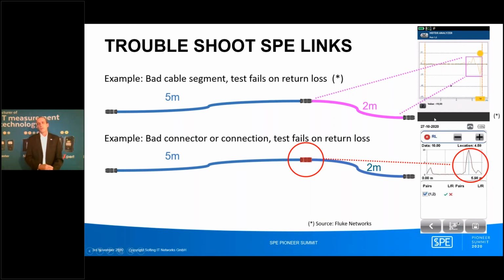With these additional functions, you can do a lot of troubleshooting in the field when you have a failed cable, and find out where along the cabling channel the problem is. I should note that both these tests have no limit lines, because the cabling standards focus on RF parameters and don't really offer limit lines here. So it's basically a subjective view of whether one connector is worse or better than another, but it's a very good measure in the field to show you where faults are.